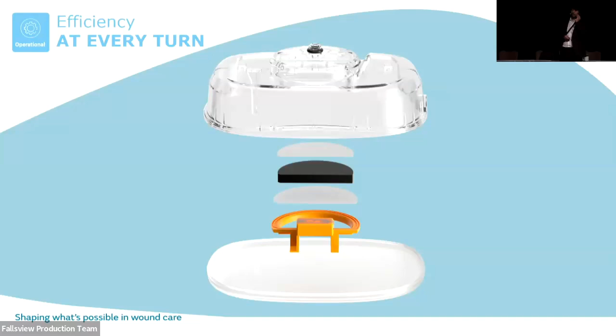Thank you. The canister construction historically has been suboptimal from a few different perspectives, because the O-ring that interfaces between the canister and the device used to be on the device side. So we realized that if we keep it on the device side, we have to maintain it. So we have to send the device somewhere. Someone has to change this thing over. So we actually switched the location of the O-ring seal, and that's now part of the disposable canister.